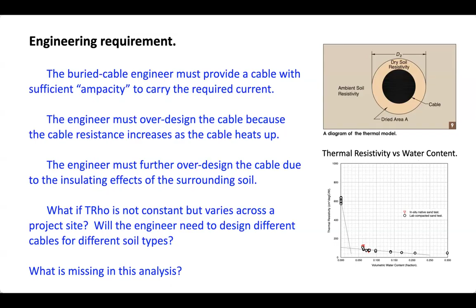The buried cable engineer must provide a cable with sufficient ampacity, as they call it, to carry the required current. And they must over-design the cable because the cable resistance goes up as the cable temperature goes up. The engineer must further over-design the cable due to the insulating effects of the surrounding soil. If this were a cable hung in the air, like a normal transmission system, heat dissipation wouldn't be a problem. But when it's underground, it cools off much more slowly. So they have to over-design for these factors. And so what if the thermal resistivity is not constant but varies across a project site? Will the engineer need to design different cables for different soil types? And so what's missing in this analysis?